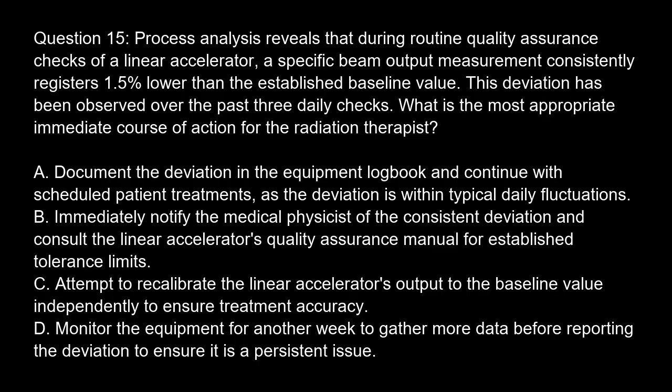Process analysis reveals that during routine quality assurance checks of a linear accelerator, a specific beam output measurement consistently registers 1.5% lower than the established baseline value. This deviation has been observed over the past 3 daily checks. What is the most appropriate immediate course of action for the radiation therapist?